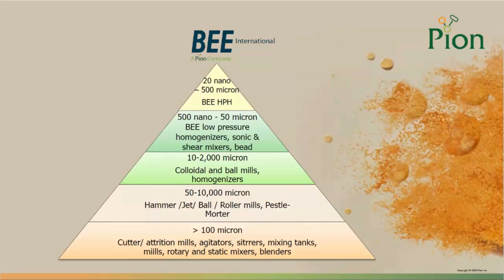BEE systems are designed to withstand higher operating pressure, with normal working pressures up to 45,000 psi. More constant operating pressure leads to reduced variation in process and a tighter distribution of results.